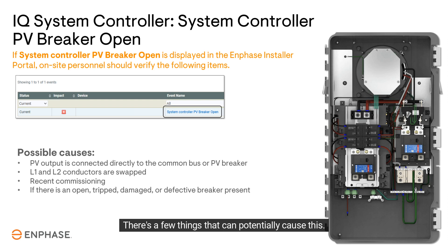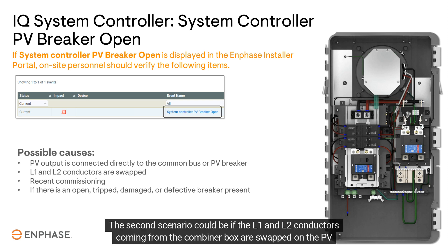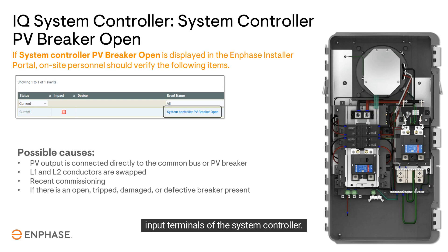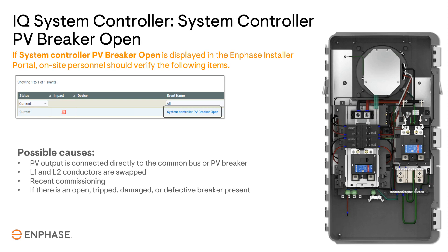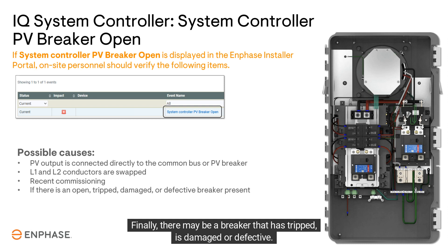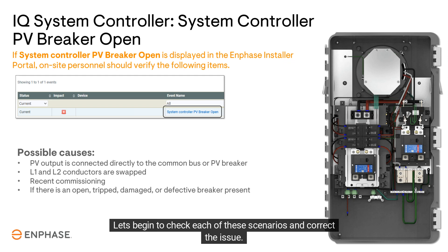There are a few things that can potentially cause this. The first is if the combiner box's output conductors are wired directly to the system controller's PV breaker on the bus bar. The second scenario could be if the L1 and L2 conductors coming from the combiner box are swapped on the PV input terminals of the system controller. The third scenario may be if the site was commissioned in the last two to three days, the PV breaker might be left open from commissioning. Finally, there may be a breaker that has tripped, is damaged, or defective.